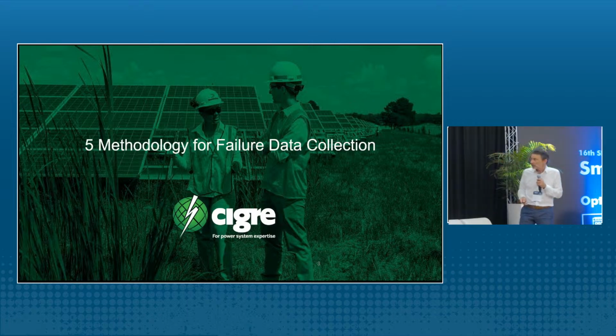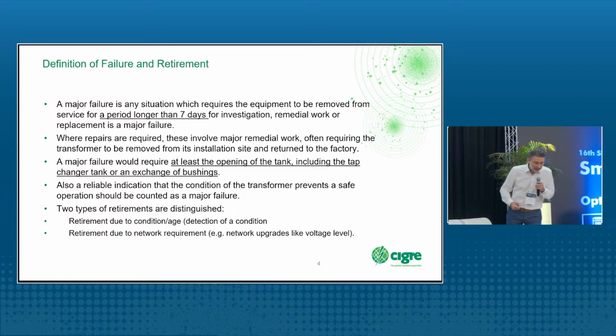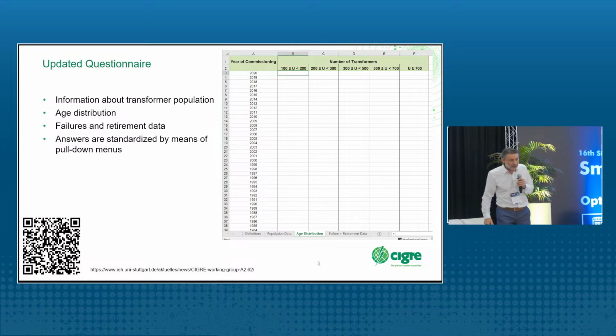So we established a questionnaire to collect this failure data. Before you start, first you have to define what is a failure. We said a failure is something where the transformer is more than 7 days out of operation. Maybe it can be repaired, or it must be scrapped. But it is not a major failure if, for example, a relay for controlling the cooling unit fails. You can exchange the relay and everything is fine again. A major failure requires oil treatment. You have to release the oil from the transformer. You have to exchange the bushing. These are major failures. And then we ask the utilities for data.